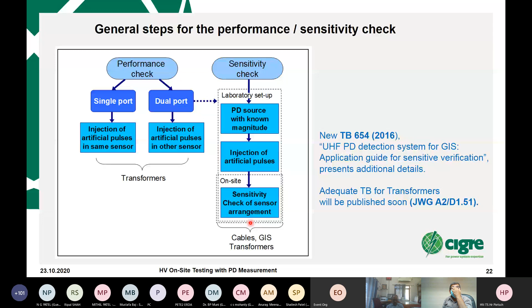There's also a sensitivity check, briefly described here. As I said, this technical brochure gives hints on how to prepare. The difficulty with a PD measurement is that you see lots of signals, dots, on the screen - each dot representing a signal in the partial discharge pattern - but the question is whether it is really a partial discharge in its true sense.